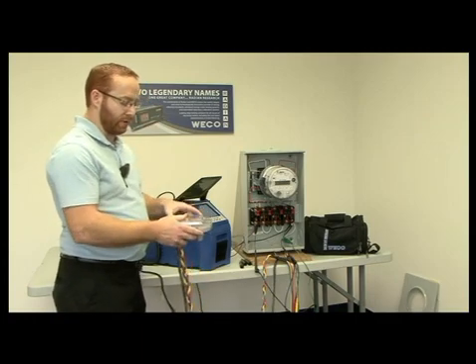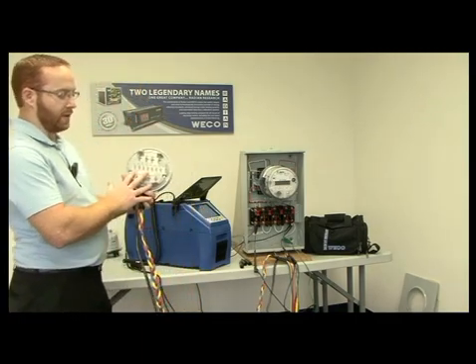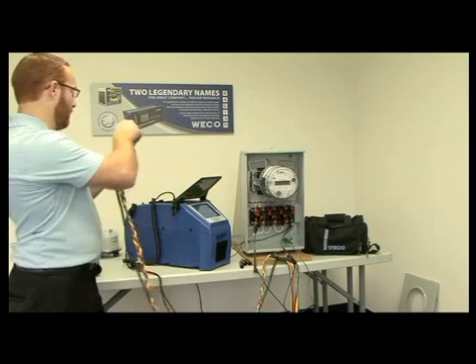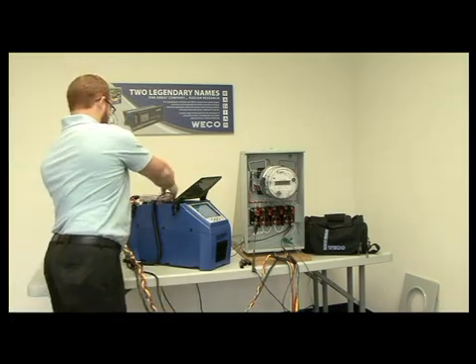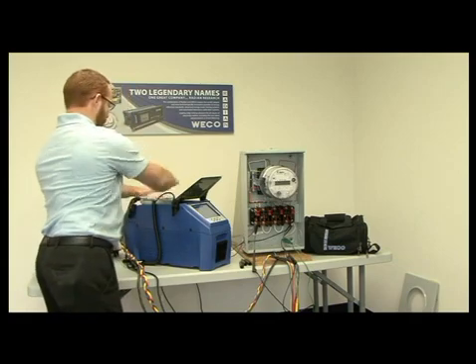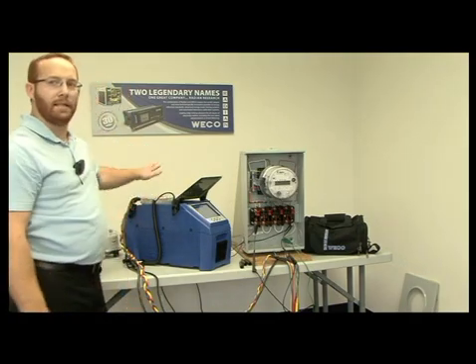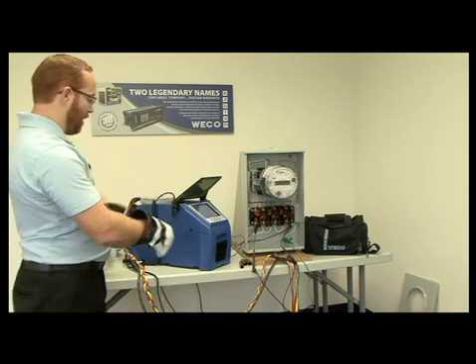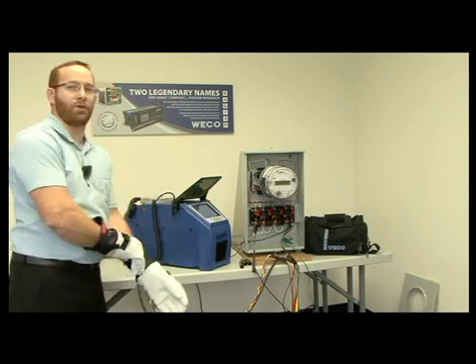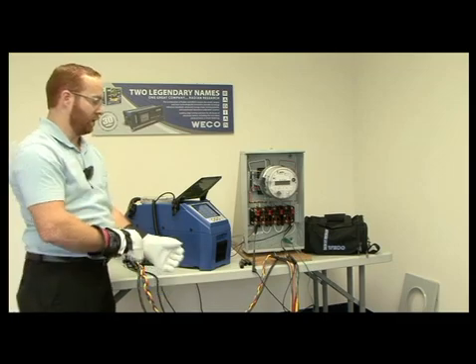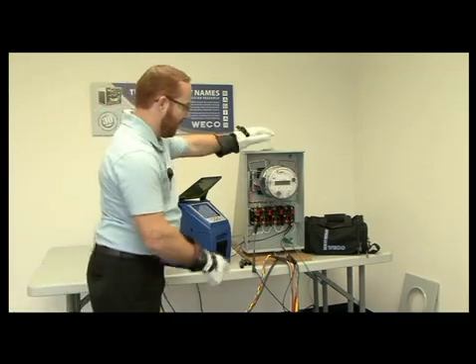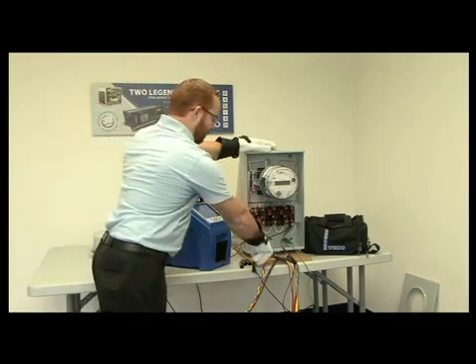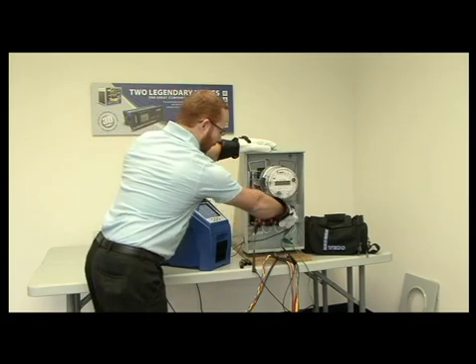The meter test adapter simply plugs into the Bantam Plus's automated socket like so. Once it's installed in the meter socket I can actually connect and configure my meter test switch to accept a sourced current and a sourced voltage. To do that I'm first going to de-energize the meter by removing all phases.